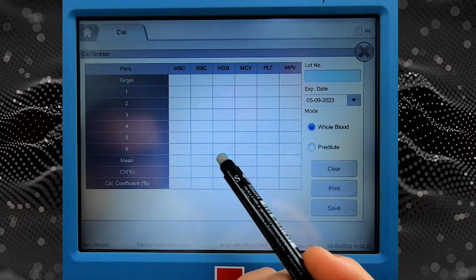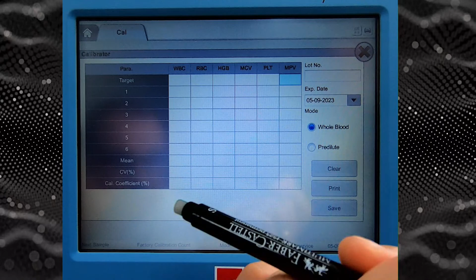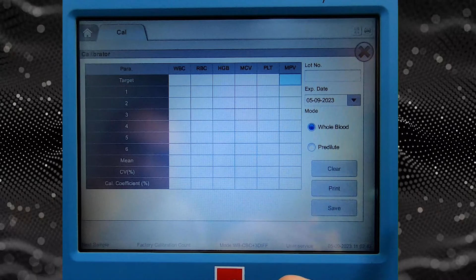The next calibration is this one. This is the whole blood or hematology calibration. We choose whole blood, put the lot number here and the expiration, of course, and we need to specify the target. Later we need to run measurements, right? 5 times minimum, even 6 on the list. Then we need to choose those repeats and just save it.